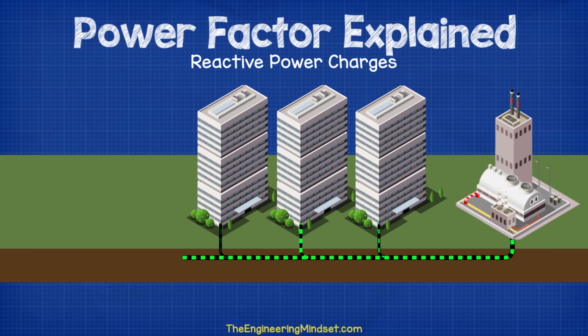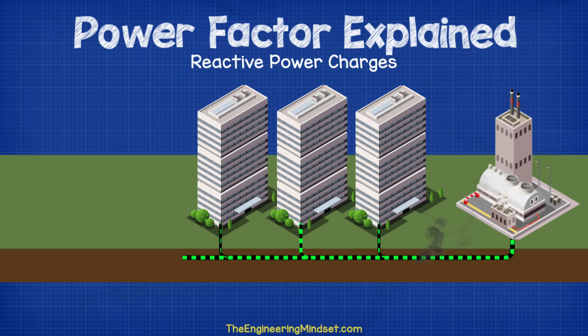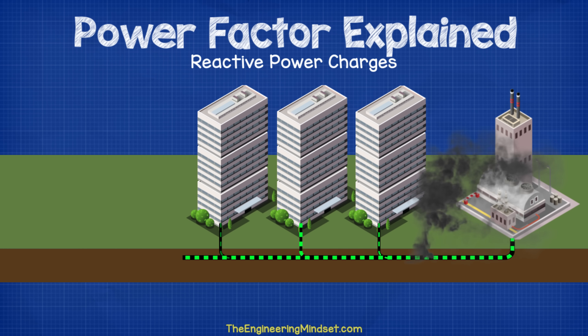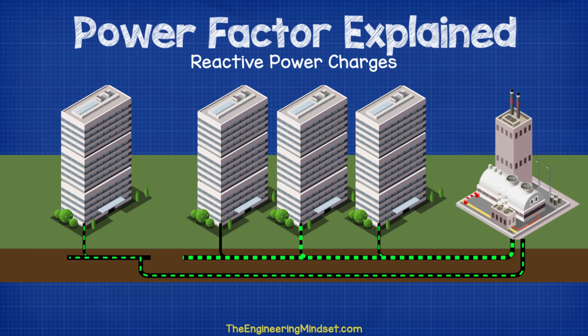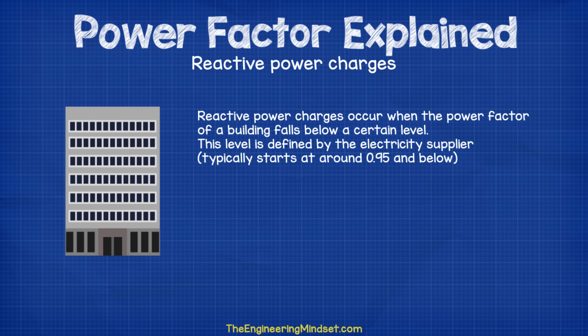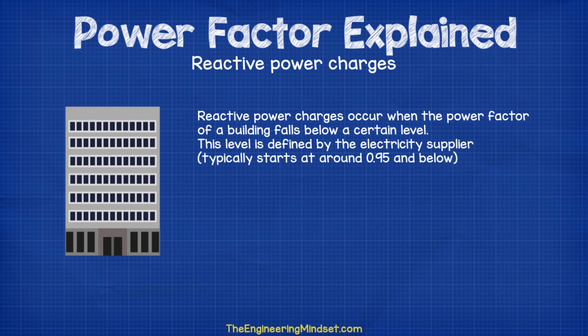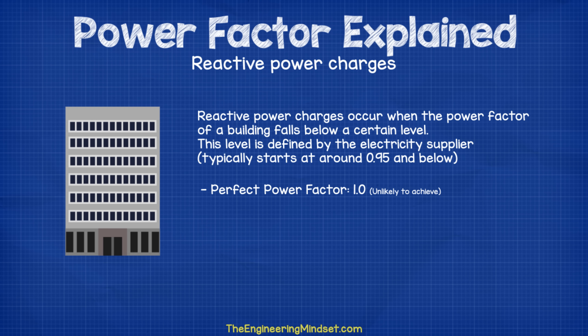Cables are rated to handle a certain amount of current flowing through them. So if a lot of large consumers connect with bad power factor, the cables could overload. They could also struggle to meet the demand and capacity agreements, and then no new customers will be able to connect until they either replace or install additional cables. Reactive power charges occur when the power factor of a building falls below a certain level, typically starting around 0.95 and below. A perfect power factor would be one; however, in reality, this is almost impossible to achieve.